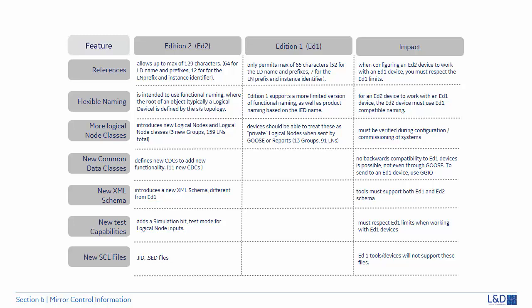On a final note, let's review the 61850 features and how they compare between Edition 1 and Edition 2. In Edition 2, the size of the field names was doubled. So when you're working with Edition 1 and Edition 2, you must respect the Edition 1 limitation. There's an expanded use of naming based on functionality in Edition 2 compared to limited functional naming in Edition 1. Once again, when working with both Edition 1 and Edition 2 devices, the Edition 2 devices must use the Edition 1 naming convention. In Edition 2, three new groups were added, and all IED functionality was mapped to a logical node. During design and commissioning, discrepancies must be verified.